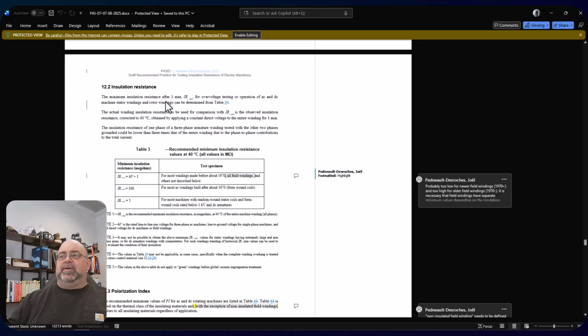So, the minimum insulation resistance for overvoltage testing or operation of AC and DC machine stator windings and rotors shall be determined from table 3. So, for overvoltage testing, the actual winding insulation resistance used for comparison, and the insulation resistance of one phase with the other two phases could be lower than 3 times that of the entire winding due to phase-to-phase contributions of the total current. So you can't test one phase at a time and then add them together. So this is meant to determine if you're going to go on to higher voltage tests.